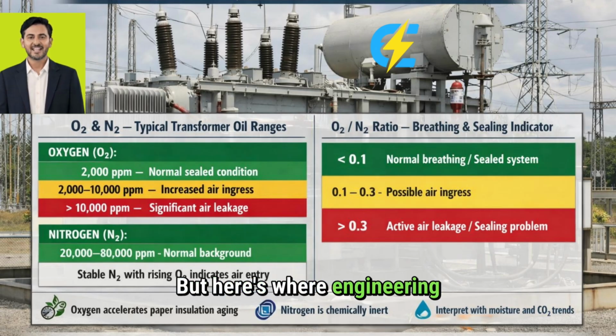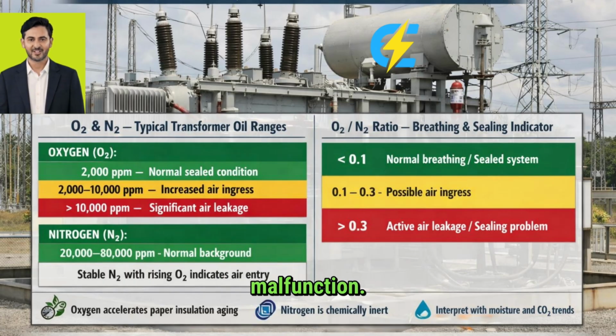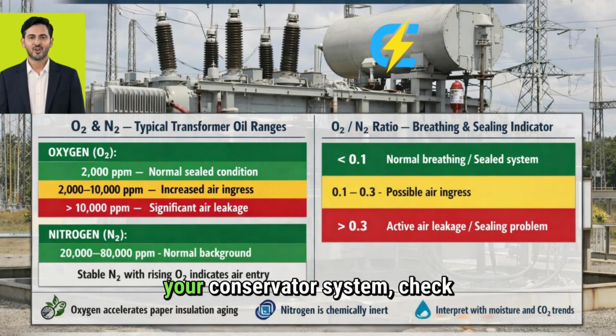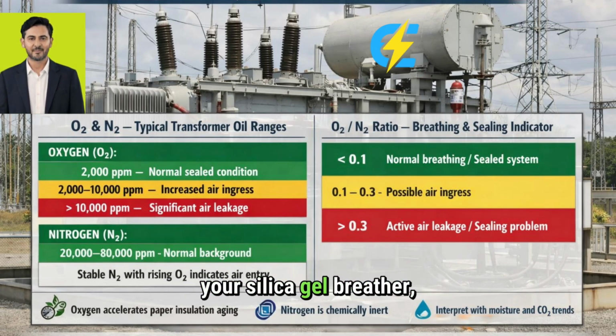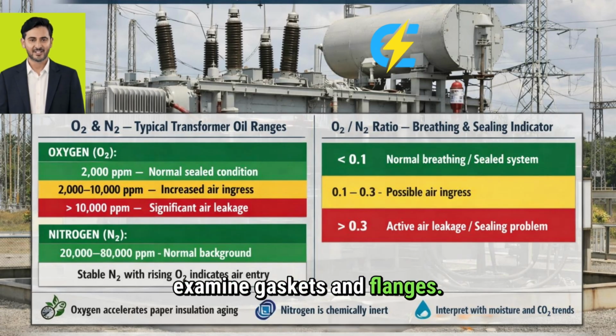But here's where engineering interpretation becomes crucial. An increasing O2/N2 ratio over time suggests excessive air ingress or breather malfunction. The action is mechanical, not electrical. You need to inspect your conservator system, check your silica gel breather, examine gaskets and flanges.